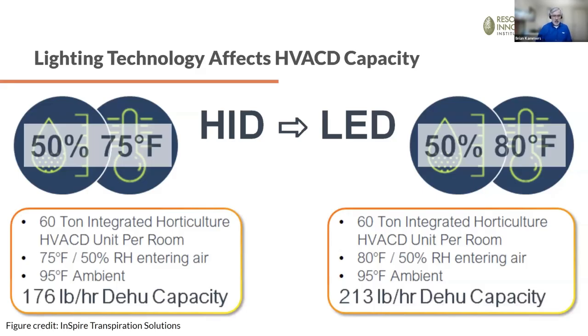Now, light has a big impact on the HVAC. HID lights use more energy, and they have a lot of infrared heat that warms up the leaf temperature. And it's really the VPD at the leaf temperature that you're trying to control. So lights that use more energy tend to need more equipment. And because you're trying to offset that infrared heat being absorbed by the leaves, you tend to run the rooms cooler. And I think we mentioned before, the cooler and drier you go with equipment, the less ability it has to remove moisture. It's less efficient at controlling the humidity.